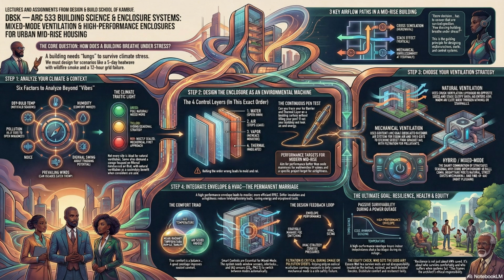If you don't design those vertical stacks, the stack effect will just try to pull air through random leaks in your floor slabs and utility chases, which, again, compromises your air tightness. The red arrows have to be intentional. Okay, so now when that climate traffic light turns yellow or red, we have to rely on mechanical systems. And the core of a modern system is often the DOAS.